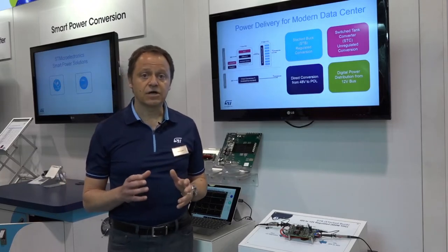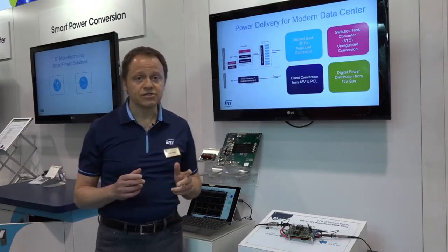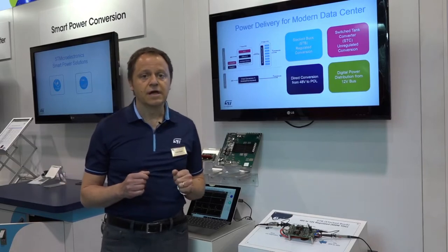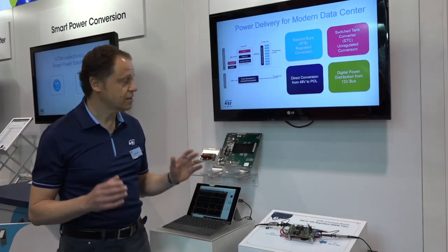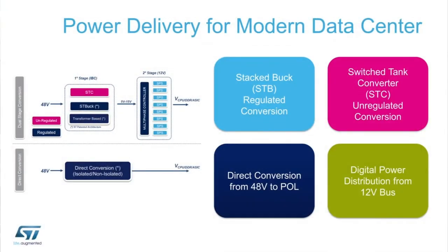ST offers a wide range of products for managing the 48-volt conversion, and particularly we have two classes of products or architectures. The first is a dual-stage conversion, where we convert from 48 volts down to an intermediate bus and then from that intermediate bus straight to the CPU or digital point of load. The second class is a direct conversion from 48 volts down to the point of load.